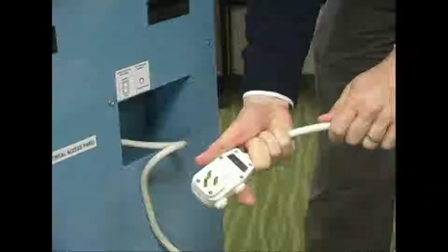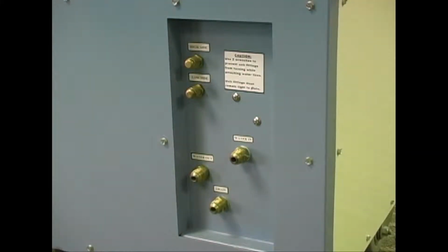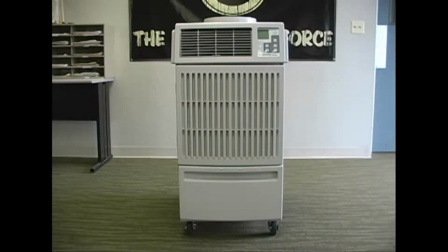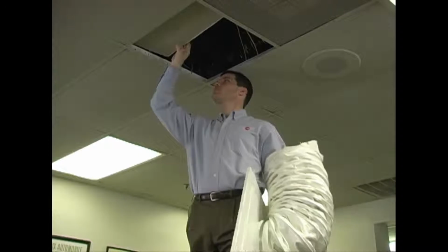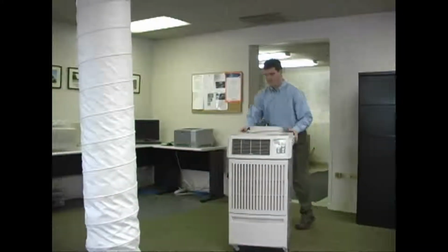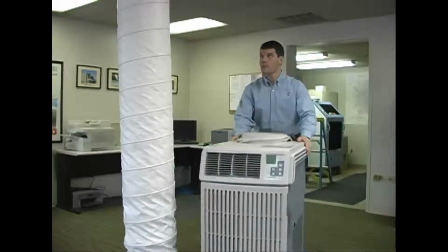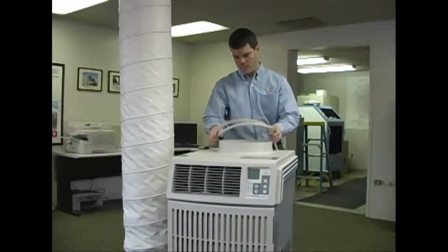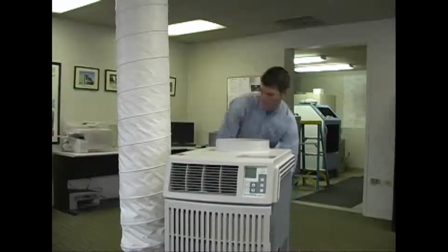Now that you have viewed the video regarding the refrigeration cycle, let's explore the air-cooled and water-cooled units. The more common type of portable air conditioner is the air-cooled unit. An air-cooled unit uses a fan, or air, thus the term air-cooled, to remove the heat from the condensing section of the unit. What this means to you when using an indoor portable air-cooled unit is that you need a space to vent the heated air, which is being removed from the condenser section of the unit.